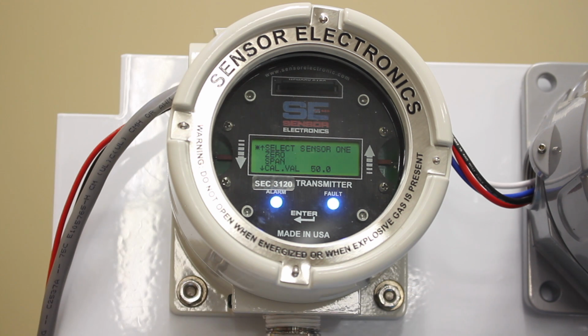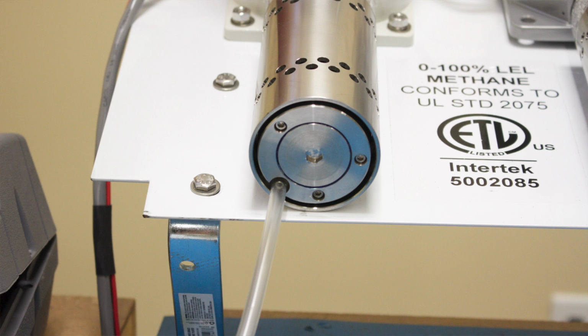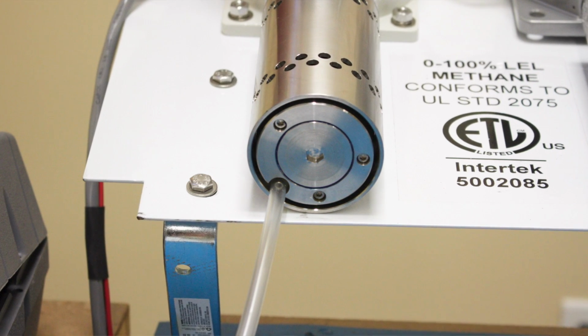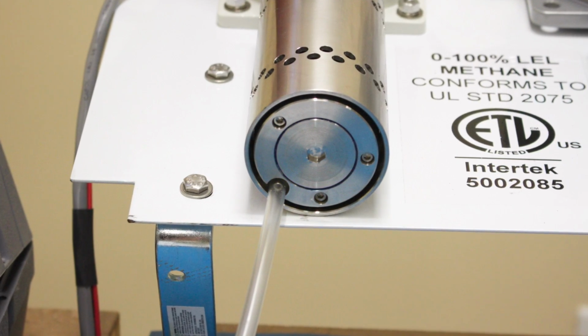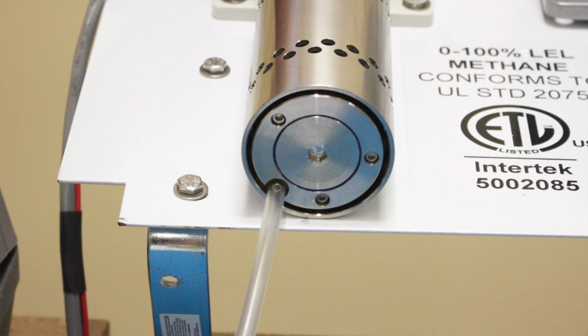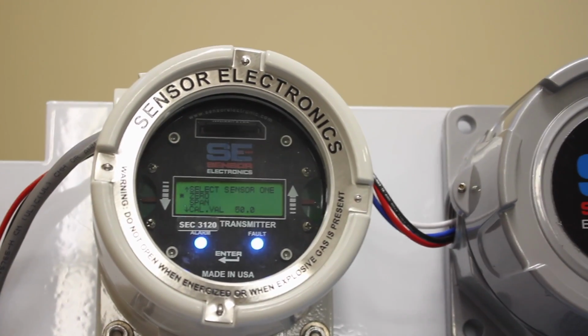And the first procedure that you want to do is, with the magnet, you arrow down to 0. So if it's in a clean air environment, you can use the ambient air to zero the sensor, or if it has background gas in it, you'd connect a clean air source, either clean air or nitrogen, and you'd connect it to the calibration port on the sensor. Down below here there's a little barb fitting where you connect your tubing up to, and we'll see that in a minute when we go to the spanning.